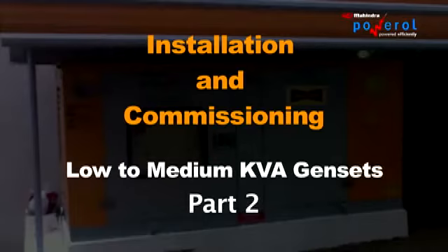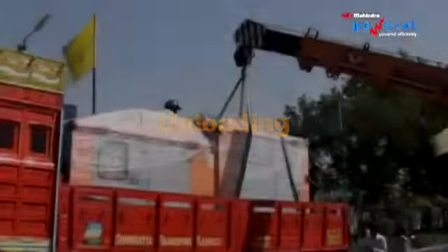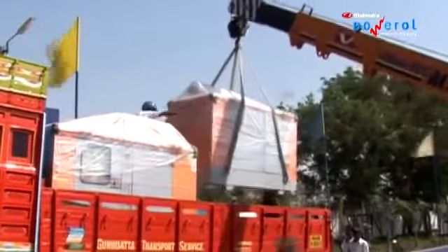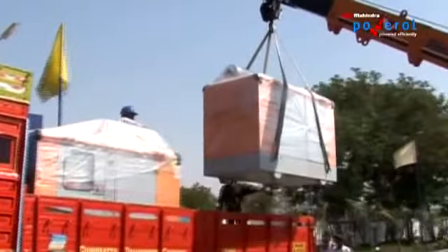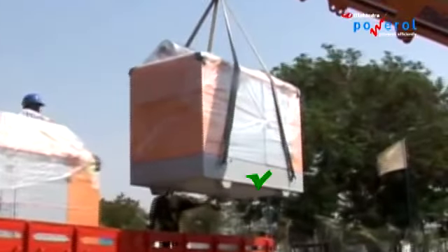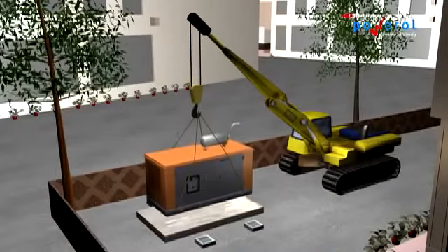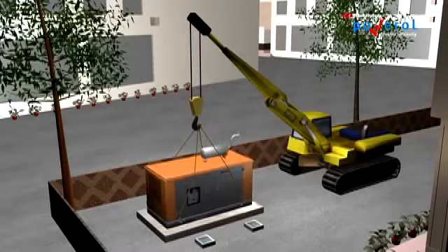Installation and commissioning. Low to medium kVA canopy gensets. Unloading. To lift the genset, use the hook provided on the canopy. Ensure that the lifting tackle is of sufficient strength for the DG load. Keep all personnel away from the DG set when in suspended position.